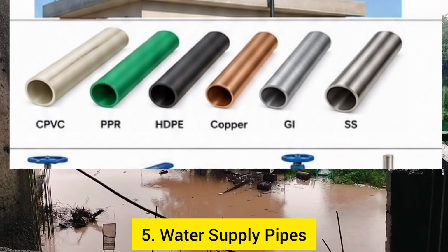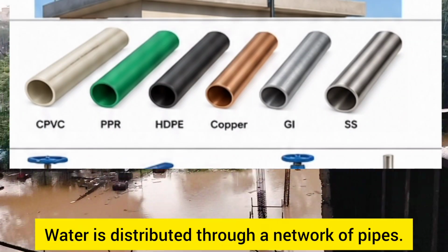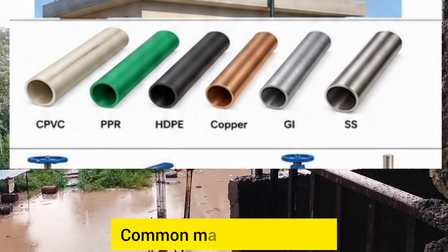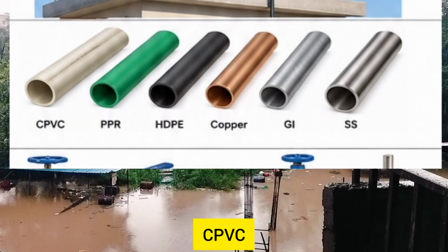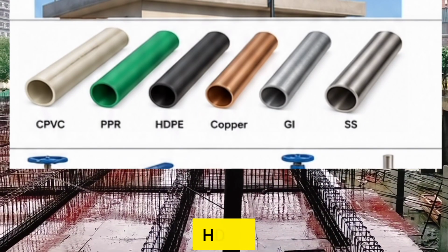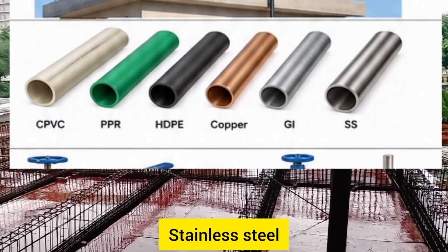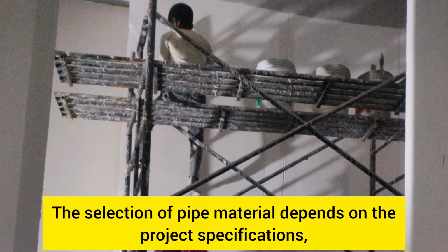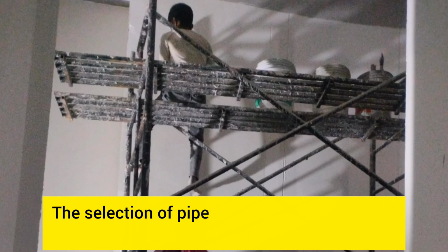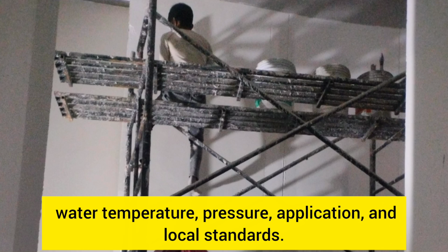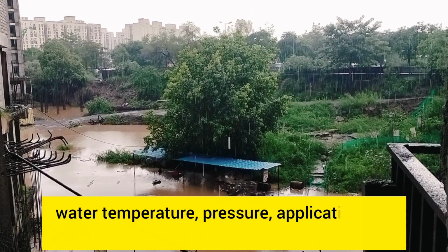5. Water supply pipes. Water is distributed through a network of pipes. Common materials include CPVC, PPR, HDPE, copper, GI, and stainless steel. The selection of pipe material depends on the project specifications, water temperature, pressure, application, and local standards.